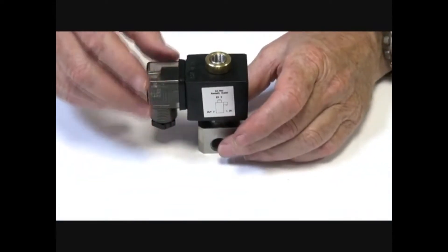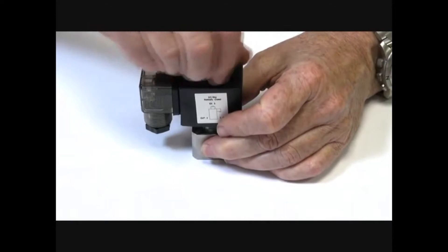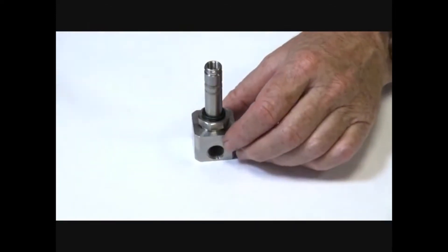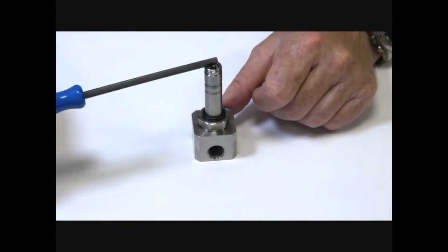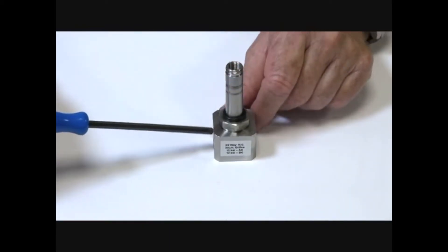Your supply is in port one, out port two, and exhaust port three. When the valve is de-energised, port two is connected to the top exhaust, and port one is the main supply waiting.